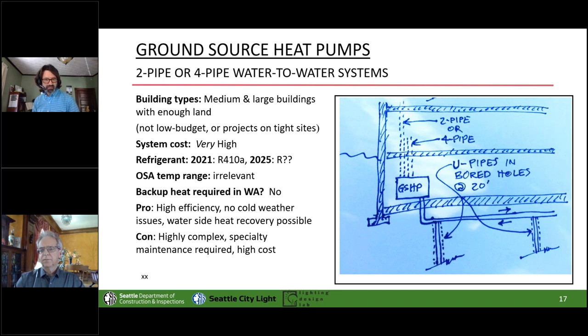The only asterisk to this is they cost a lot. That well field costs a lot, but it also lasts many system changes. So you've baked that into the project for the next, we know it lasts at least 50 years and we suspect much longer, maybe as long as 100 years. And then the other giant asterisk is that you have to have somewhat balanced heating and cooling loads, or you will slowly drive your ground temperature up or down. Schools are a famous example because they don't really run cooling in the summer. So their ground slowly cools off over the first 10 or 12 years, and they get less and less efficient the longer that goes. Now, there are some asterisks.